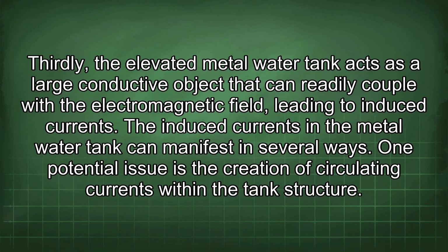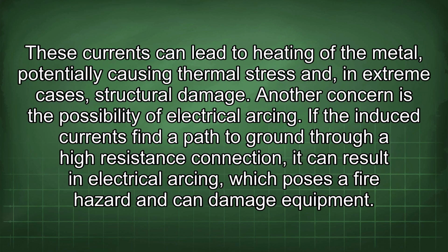The induced currents in the metal water tank can manifest in several ways. One potential issue is the creation of circulating currents within the tank structure. These currents can lead to heating of the metal, potentially causing thermal stress and, in extreme cases, structural damage. Another concern is the possibility of electrical arcing. If the induced currents find a path to ground through a high-resistance connection, it can result in electrical arcing, which poses a fire hazard and can damage equipment.